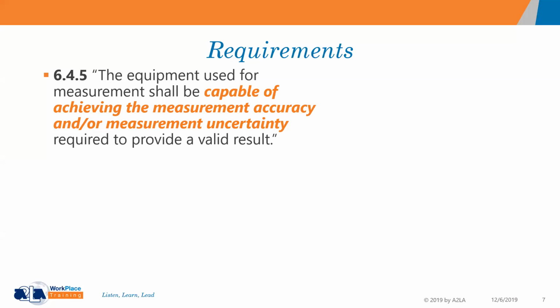So the first clause, 6.4.5, says equipment that's used for measurement shall be capable of achieving the accuracy and/or measurement uncertainty that is required to provide a valid result. And if you remember from that previous slide, I gave an illustration of what accuracy and uncertainty is. If you have questions about that, we can discuss that later on in another slide. But the point here is making sure that you have your eyes set on accuracy and uncertainty, which is a little bit different from what we had in the 2005 version of the standard.